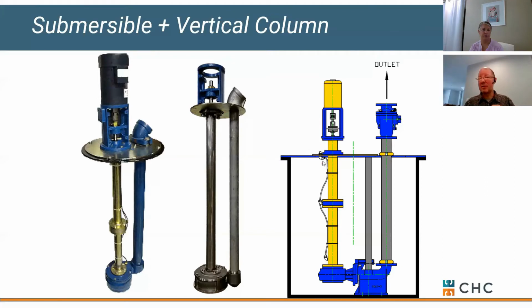It might look easy to service, but if you've got to pull a 10-foot vertical column out of a sump, you better have some ceiling height above you. Our rule of thumb is we tend to do a lot of submersibles. Vertical column is usually 4 feet or less as far as that basin goes. So we just have to be careful on that application. We used to see a lot of them, but more commonly we're seeing them go away a little bit. There's nothing wrong with them. You just have to be careful on their application.